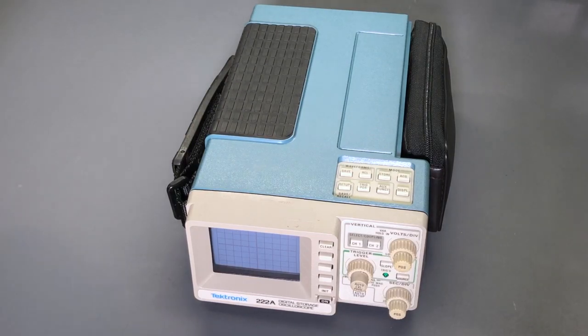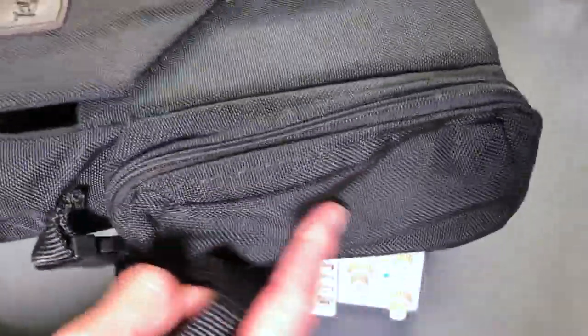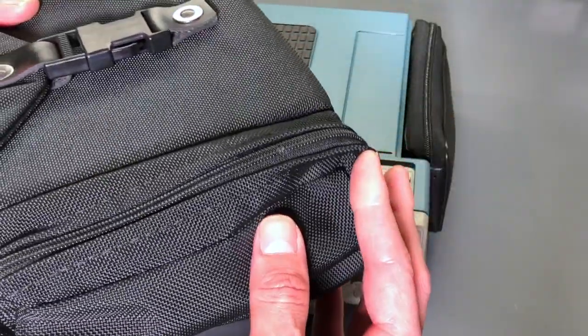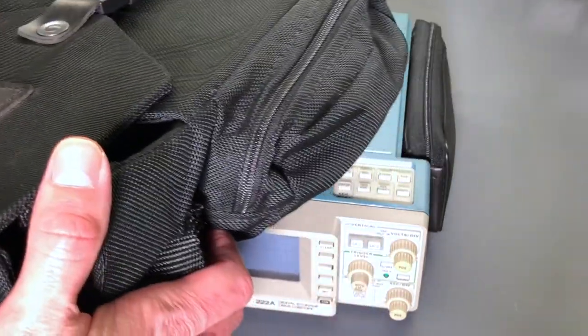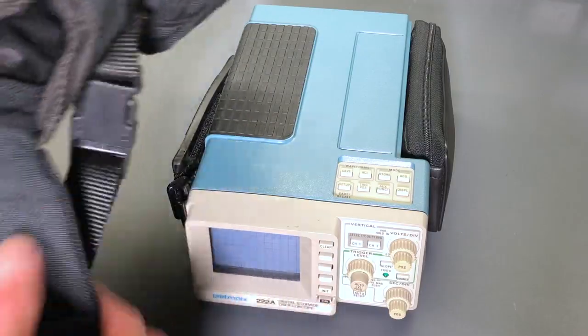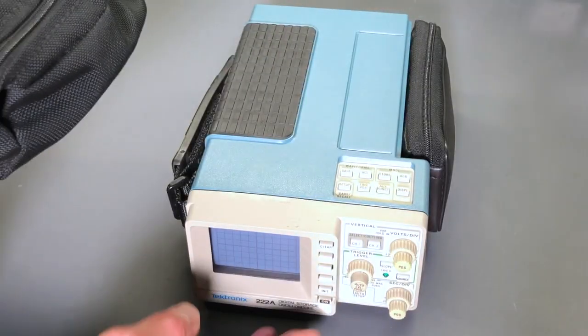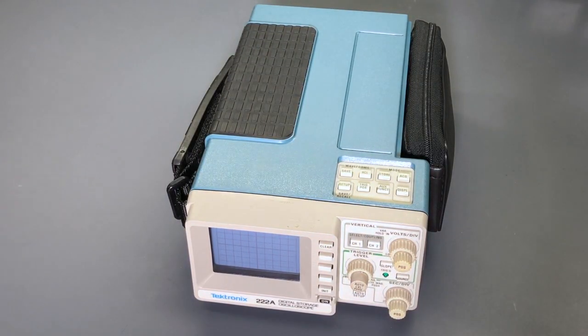Also there's a carrying case that goes with it, a nice original case with more storage on the side over here. You can unzip that and unzip the side so that the probes can come through and it can be in here. One thing you want to watch out for is the power button on the front. You don't want it to be touching the front when this flap closes and ends up actually turning on the scope. You need to watch out for that. But otherwise a well-made case and nice to have that as well with it.